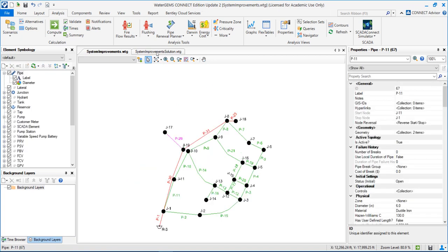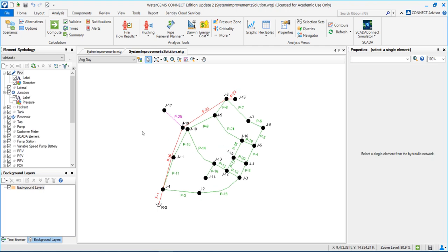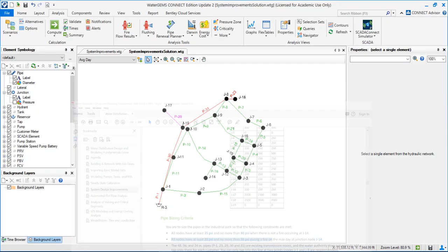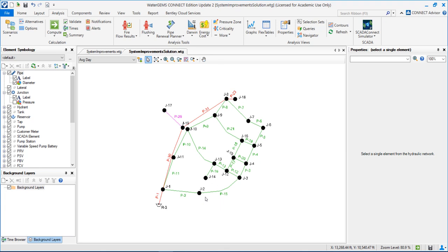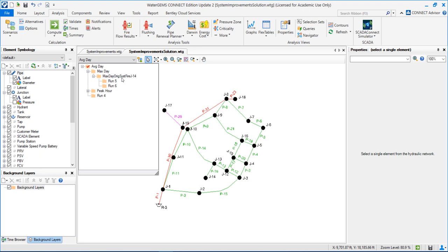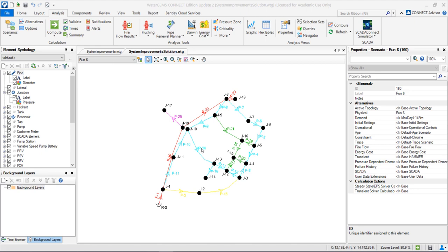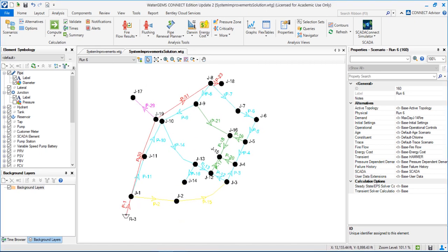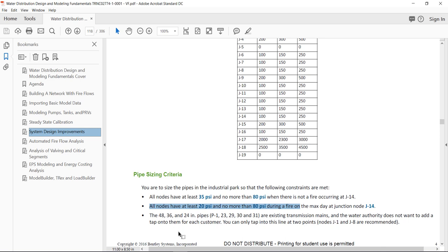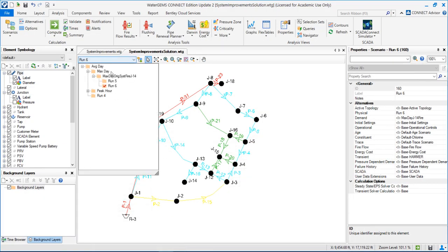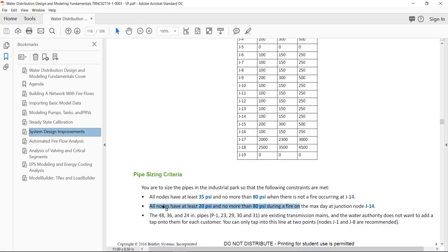Let's move to the solution. This is a proposed solution — there are other possible solutions to achieve the requirements. We tried different scenarios combining different pipe sizes: run 4, run 5, run 6. Run 6 was the only one that achieved all requirements at the same time. We can select run number 6 and check the first criteria — that all nodes should have at least more than 35 psi.